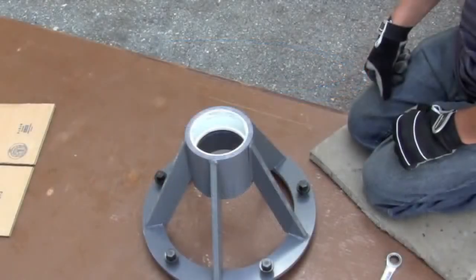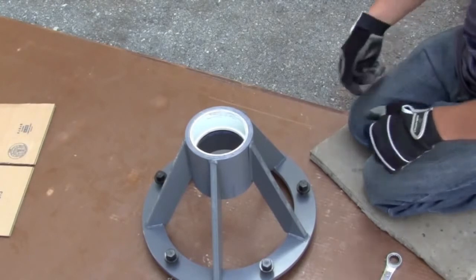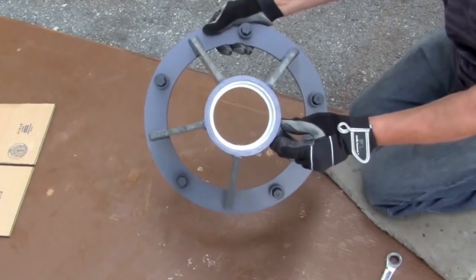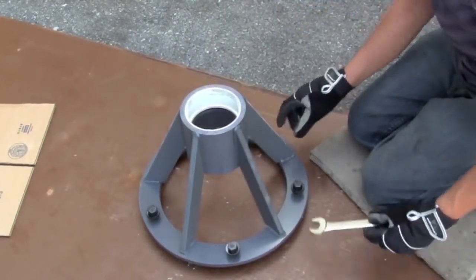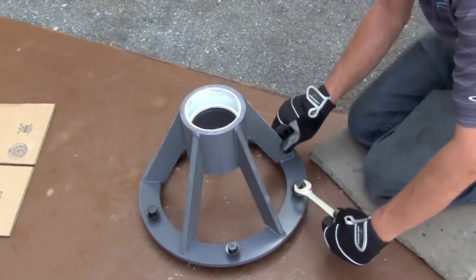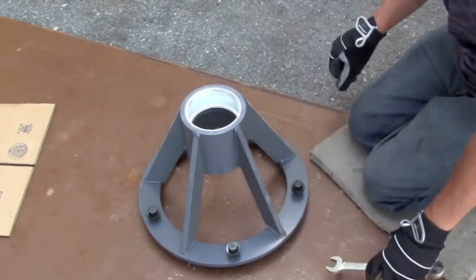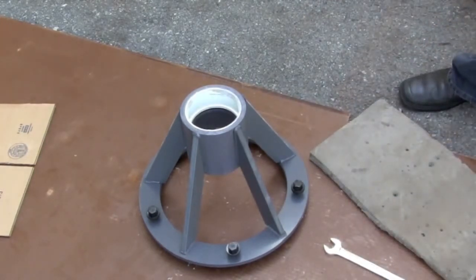Our non-invasive internal pipe support is used for safe tanks or when a bolt through the side wall is not desired to support your piping. The support will come with a reducer already installed in the center to fit the pipe size that you've ordered. The bolts on the bottom of the support can be adjusted with a three-quarter inch box wrench to achieve a level surface on the bottom of the tank. The pipe itself does not need to be glued into the support.